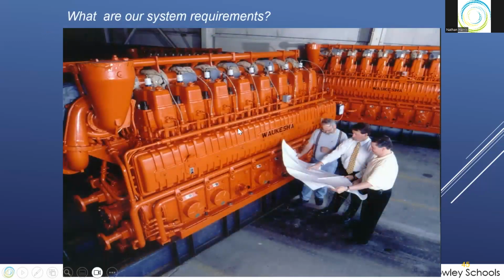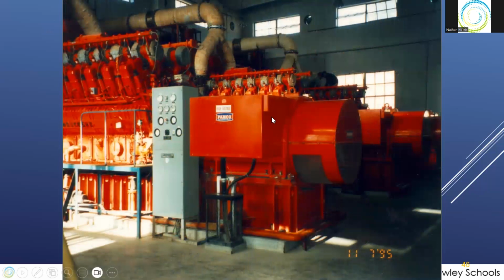So we're going to look at one real quick here. And obviously, this is a big old gas Waukesha. See the coils and the steam lines and all that up here. So the level of control here is going to be different. And here's the generator with its medium voltage. I can tell because there's no breaker here. It uses differential relaying to accomplish that. But the control panel on here is basically a monitoring panel. It's probably monitored somewhere else. So the controls on there would be maybe 5 or 10% of the cost of the machine, but still, you want to protect it. It's a very expensive machine. You want to provide as much control and protection as possible to minimize outages, minimize faults, things like that.